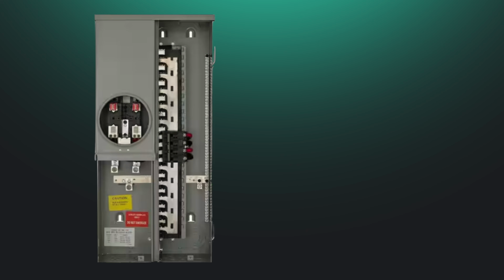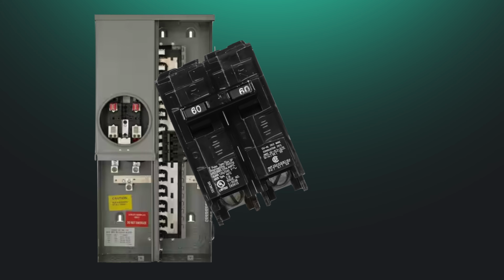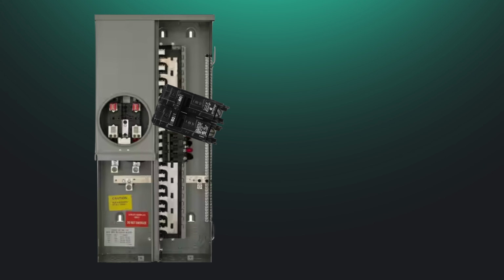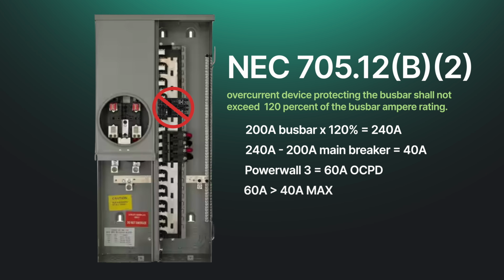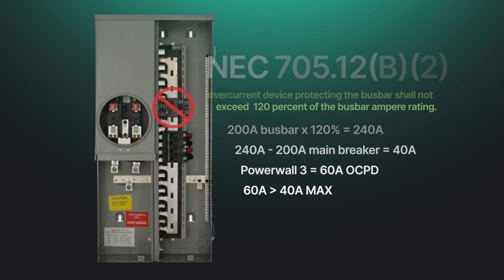Now, let's apply this to a real-world installation. The Tesla Powerwall 3 inverter requires a 60 amp breaker, so immediately we have a problem. The Powerwall 3 needs 60 amps, but the panel only allows 40 amps under the 120% rule. Since 60 amps is greater than 40 amps, the installation would not comply with the code using a standard 200 amp panel. For years, the solution was simple: upgrading the panel.